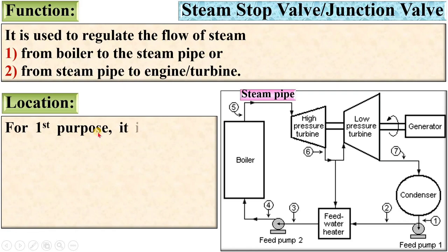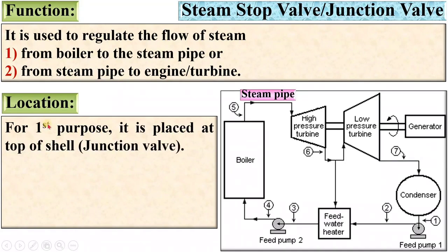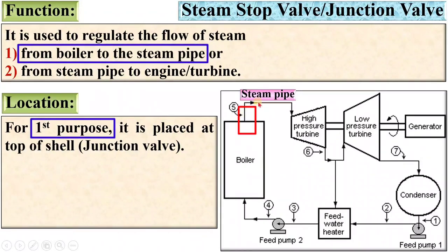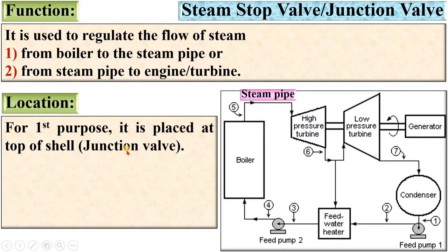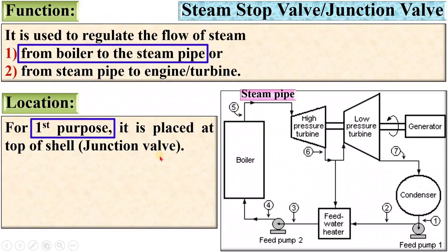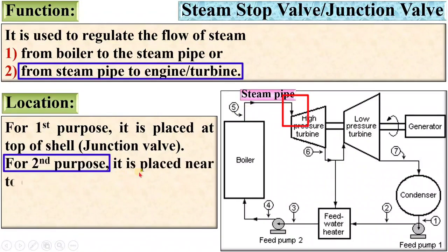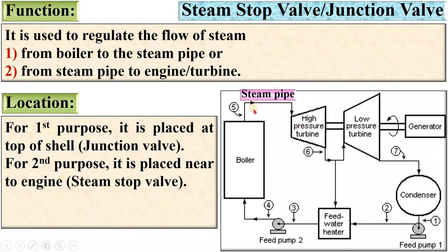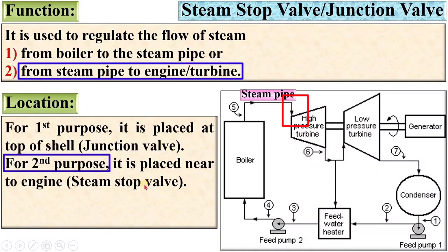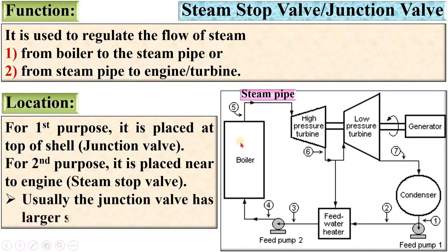Now let us see the location of the steam stop valve. For the first purpose — that is, to regulate the flow of steam from the boiler to the steam pipe — it is generally called the junction valve and is placed at the top of the shell. For the second purpose — regulating the flow of steam from the steam pipe to the engine or turbine — it is known as the steam stop valve. Usually the junction valve has a larger size than the stop valve.